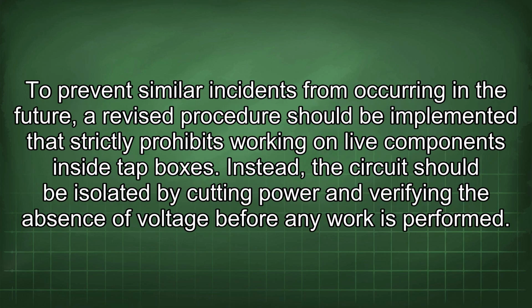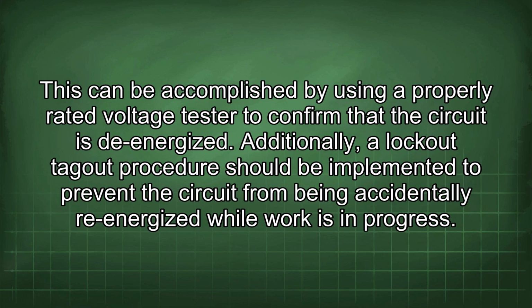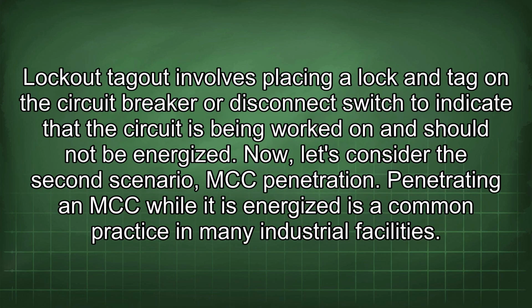To prevent similar incidents from occurring in the future, a revised procedure should be implemented that strictly prohibits working on live components inside tap boxes. Instead, the circuit should be isolated by cutting power and verifying the absence of voltage before any work is performed. This can be accomplished by using a properly rated voltage tester to confirm that the circuit is de-energized. Additionally, a lockout-tagout procedure should be implemented to prevent the circuit from being accidentally re-energized while work is in progress. Lockout-tagout involves placing a lock and tag on the circuit breaker or disconnect switch to indicate that the circuit is being worked on and should not be energized.